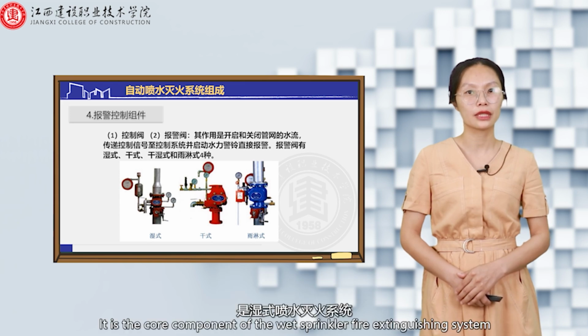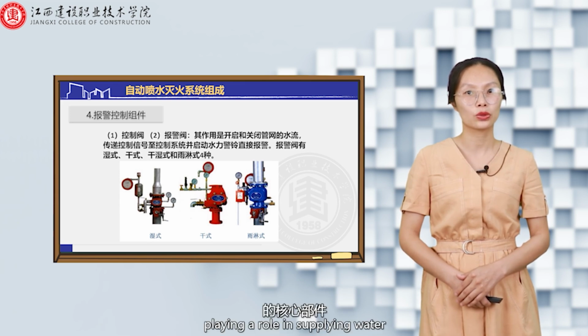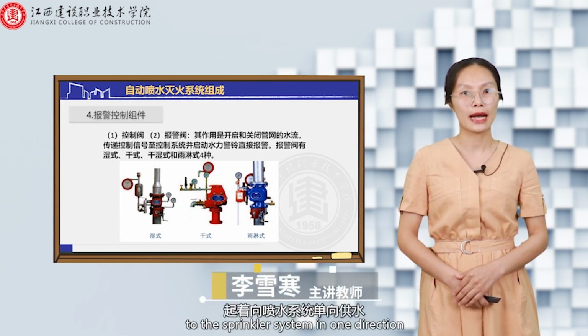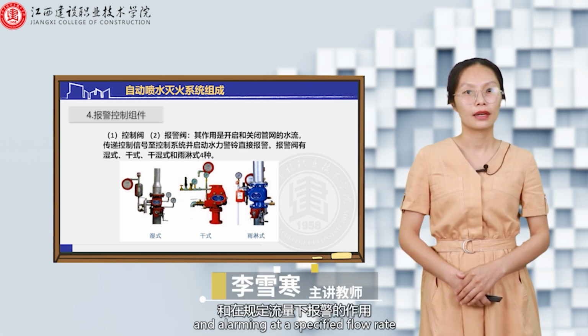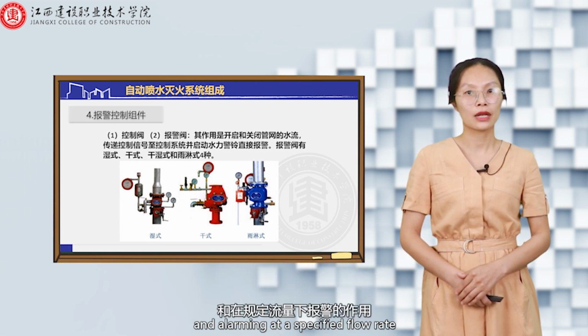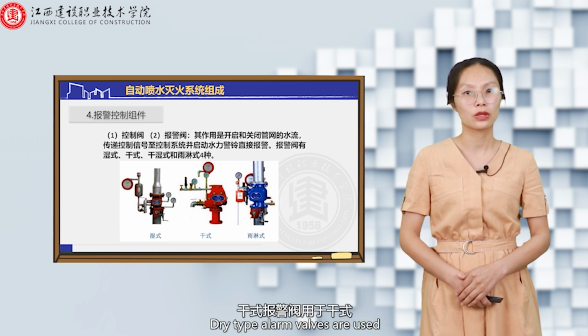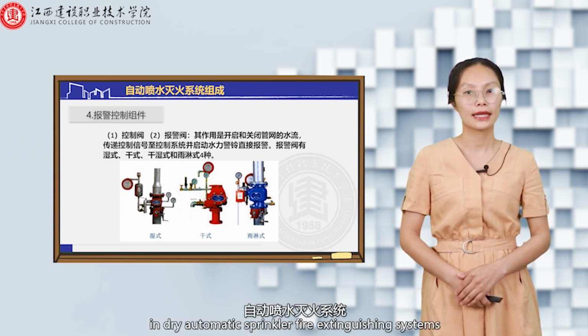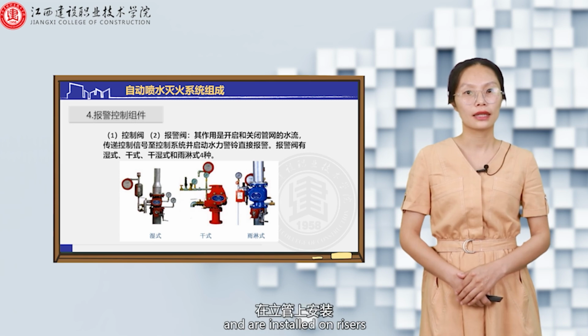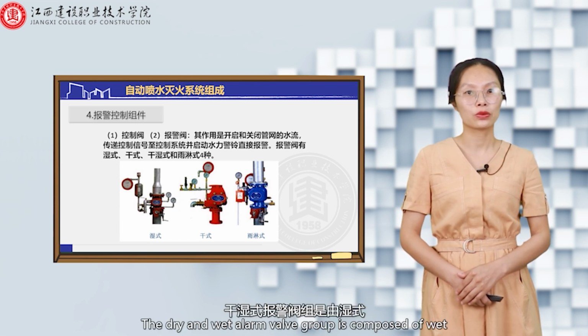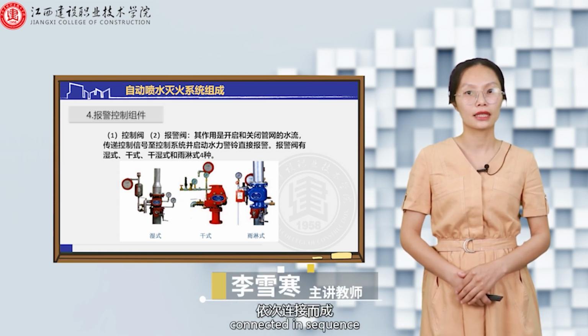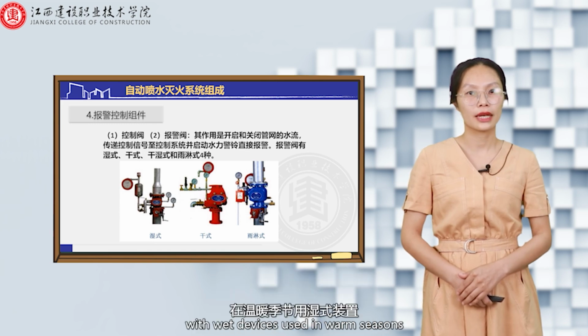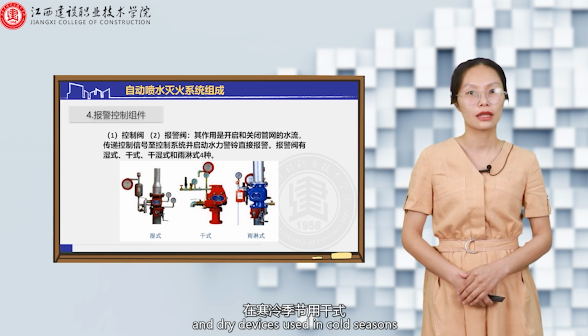It is the core component of the wet sprinkler fire extinguishing system, playing a role in supplying water to the sprinkler system in one direction and alarming at a specified flow rate. Dry-type alarm valves are used in dry automatic sprinkler fire extinguishing systems and are installed on risers. The dry and wet alarm valve group is composed of wet and dry alarm valves, connected in sequence, with wet devices used in warm seasons and dry devices used in cold seasons.